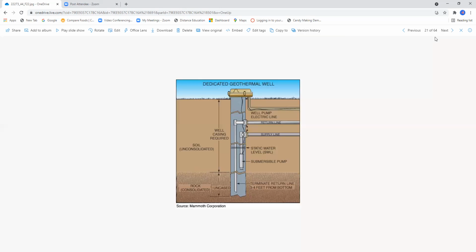This is figure 44.22. And basically, we have, of course, the electric line for the submersible pump, the return line, the supply line, submersible pump, which is plugged into the power source, the static level indicator where we want the water level to remain, and the well casing is obviously required here. The soil is what they call unconsolidated, loose, unpacked. You have rock consolidated, uncased. It terminates the return line 2 or 3 feet from the bottom.